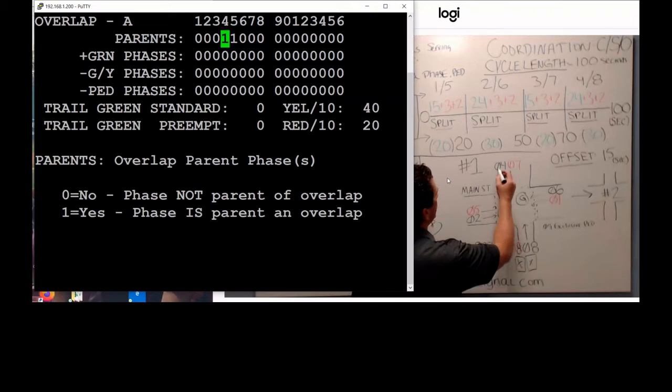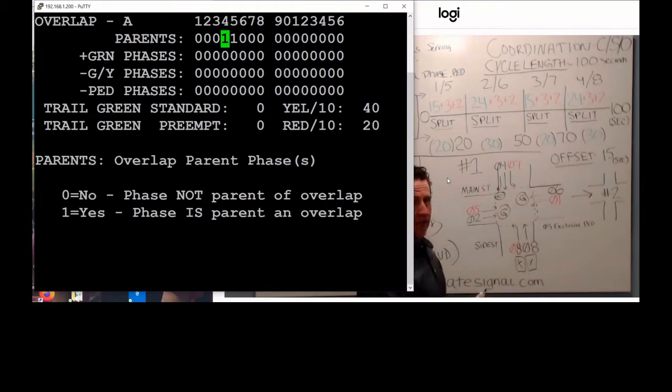And what that would be is typically if you have a right turn here. So I have a right turn arrow. That's my signal right there. So what that's saying is when phase 5 is on, I can have this right turn arrow come on, because that's not a conflict, right? We would put a little jumper in the monitor to allow those 2 phases to be on.